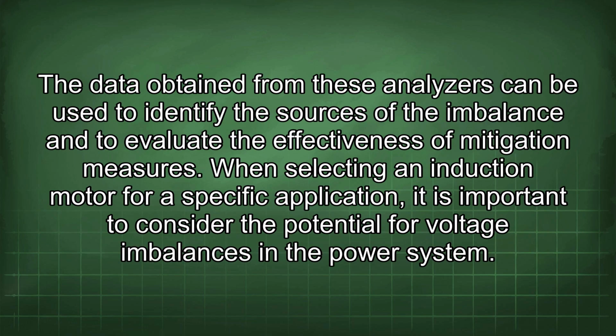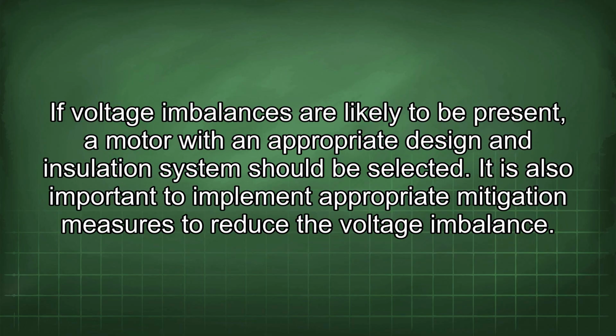The data obtained from these analyzers can be used to identify the sources of the imbalance and to evaluate the effectiveness of mitigation measures. When selecting an induction motor for a specific application, it is important to consider the potential for voltage imbalances in the power system. If voltage imbalances are likely to be present, a motor with an appropriate design and insulation system should be selected. It is also important to implement appropriate mitigation measures to reduce the voltage imbalance.